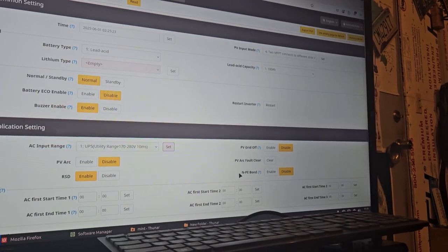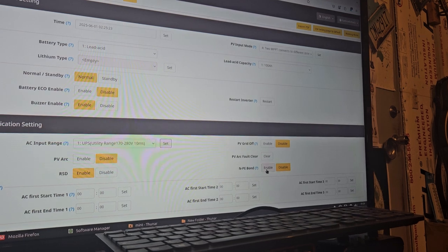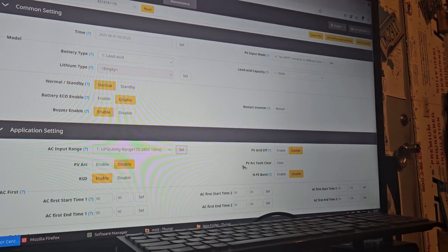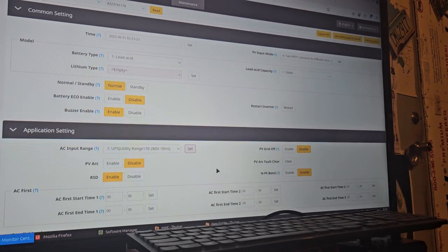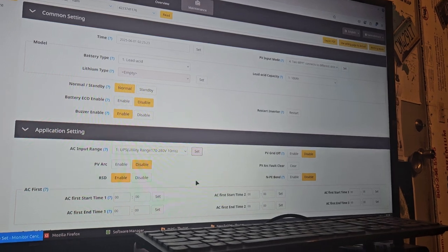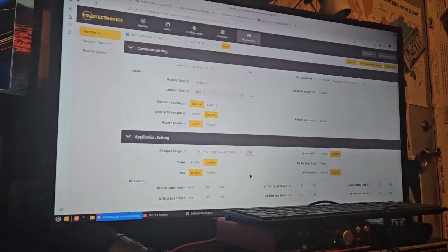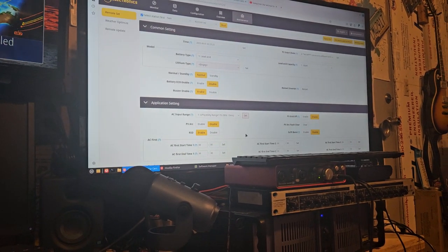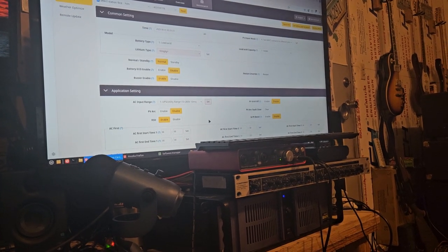You can neutral bond, enable it or don't enable it. We don't want it enabled because we're plugged into the grid, so the grid is supplementing. It's not really supplementing, because this isn't a hybrid inverter - what it does is when it reaches a certain voltage, the grid kicks on, takes over the load, and also charges the battery, or however you set it.